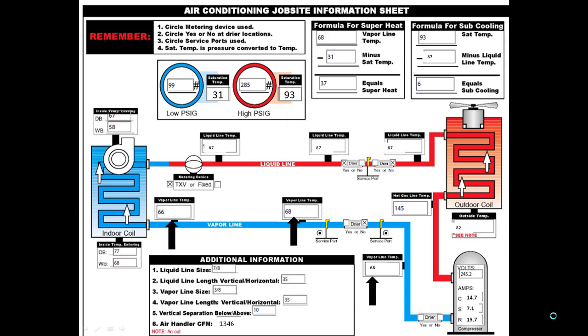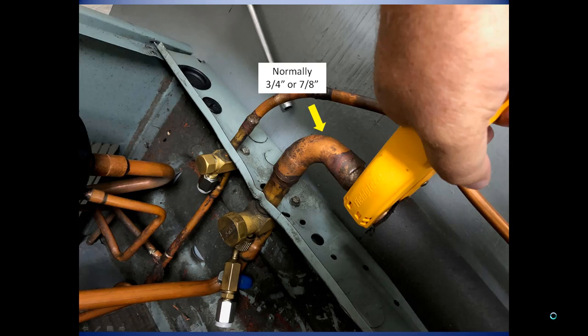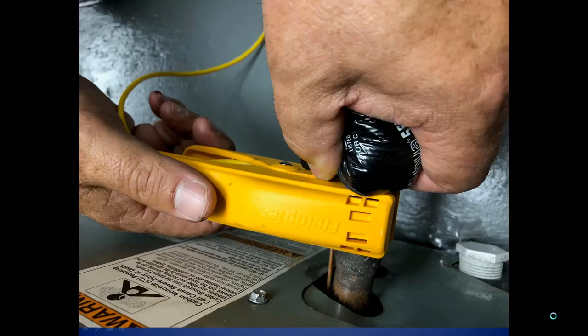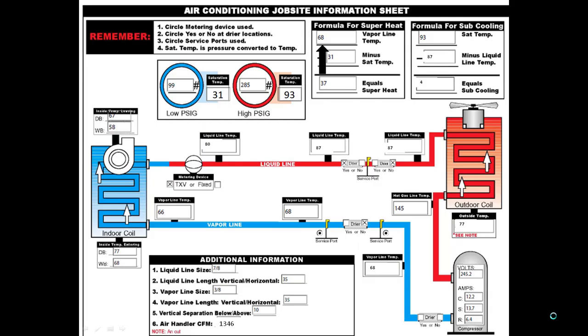We move on to the vapor line or the suction line now. We need to take those readings in 3 different places, like you see on the chart. Here's a picture at the condensing unit. Here's one at the air handler. And normally you're looking at 3/4, 7/8 copper here. Alright, we take that reading and put it right here on the pressure temperature chart.